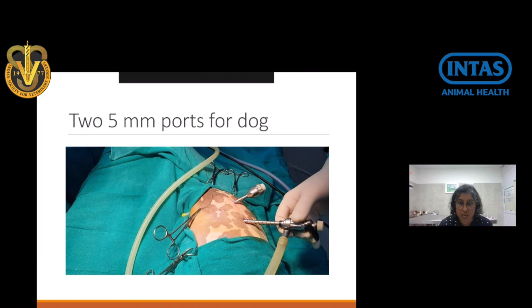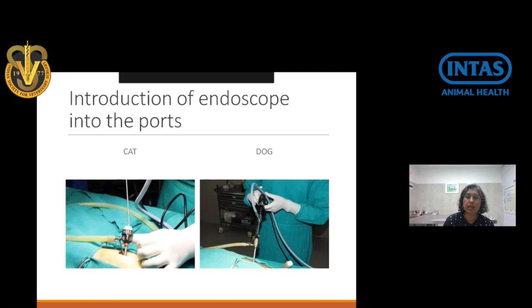Now, introduction of the rigid endoscope into the port. Once you have finished your white balancing and your ports have been placed, you introduce the rigid endoscope into the designated port. When you introduce it, your camera head should always be facing cranially towards you, and the light cable should also be grasped simultaneously. Orientation in case of a 0 degree telescope or a 0 degree rigid endoscope is basically always pointing forward. Orientation is very important if you are using a 30 degree scope, because in a 30 degree scope you can see over or you can see under. So it all depends on your orientation, and the orientation is basically if the camera and the light source are all in the same plane.